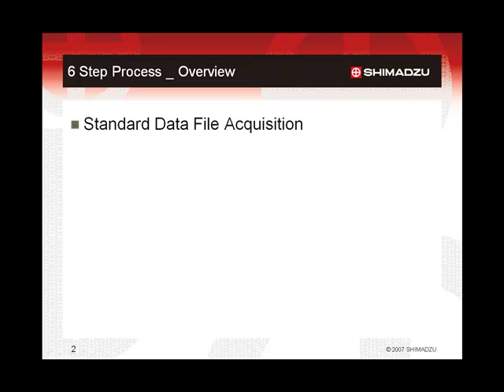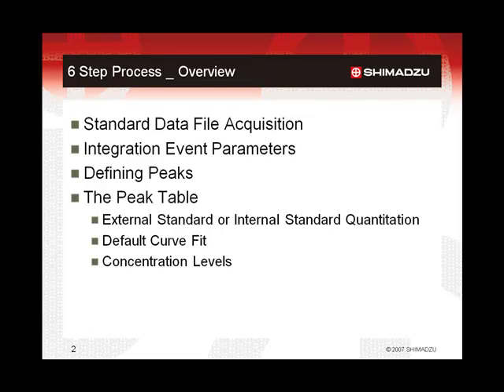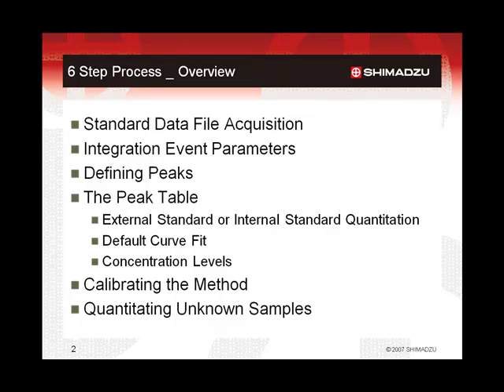The complete process involves six steps from beginning to end. This presentation will include description of all six steps, which include: standard data file acquisition; setting of appropriate integration event parameters; defining the peaks of interest for quantitation; setting the required information in the peak table, which includes choice of external standard or internal standard quantitation, selecting a default calibration curve fit, and setting the concentration levels for the calibration standards; calibrating the method based on analysis of the calibration standard data files; and using the calibrated method to quantitate unknown or non-standard samples.